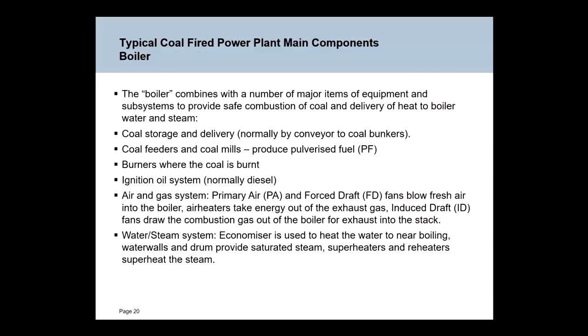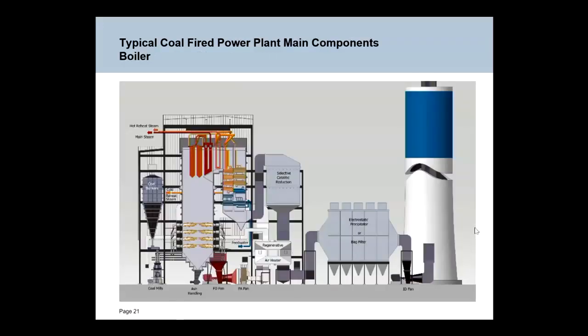All right. So if we look now at some more slides of a boiler. Again, here you can see this is more to scale of a boiler. You can't see the turbine in this picture. We've got the coal bunker, mill, 4 levels of burners either side of this particular furnace with ash dropping out of the bottom, superheater pendants, reheater and economizer in the back path, gas cleaning and the stack.